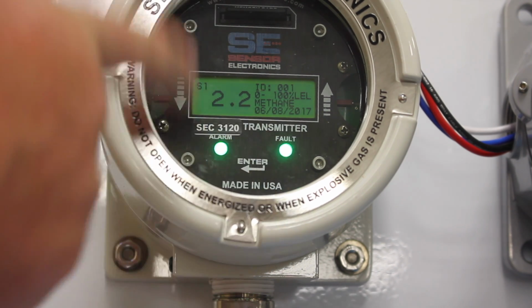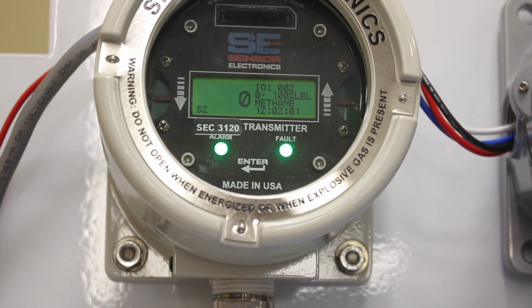See, some of the gas is going back up into the sensor, and that's what the small reading is. So eventually that gas will dissipate out of the sensor, it'll just read 0. So that's the end of the calibration of the 3120 hooked up to the Millennium infrared sensor.